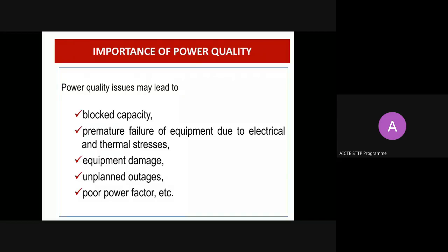The capacity is reduced. For example, the Panther conductor is designed to transfer about 85 megawatt to 90 megawatt. If the current you are passing through the conductor has more harmonics, then it is very difficult to transfer the quantum of power it was designed for. You have to use only a little less than the design parameter. That's why it creates a blocking capacity. So this is because of the power quality.